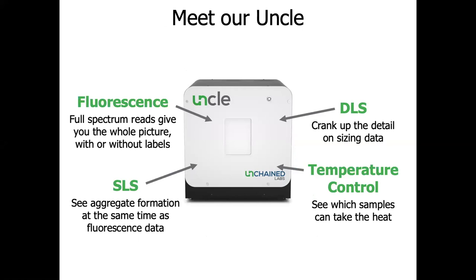This is where I would like to introduce you to the UNCLE platform from Unchained Labs. The UNCLE platform is an all-in-one biological stability platform which was built for biologics and could be an answer to many of the stability and aggregation questions that you may have. The UNCLE contains three different detection methods: fluorescence, static light scattering (SLS), and dynamic light scattering (DLS). The fluorescence gives you a full spectrum between 250 nanometers and 720 nanometers. Additionally, the UNCLE has the capability to temperature control, which can be user-defined between 15 degrees and 95 degrees Celsius.